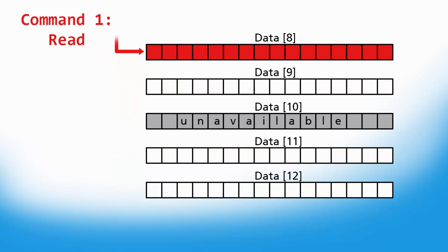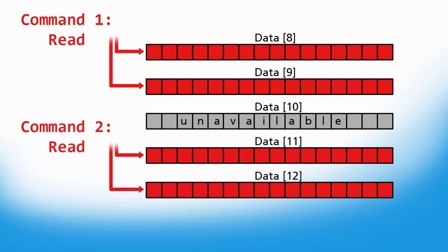You can test for this by changing the register count to 1 to see if the error clears. If so, then the solution would be to adjust your register count to ensure that you're only reading and writing to those addresses that are available. This may mean creating 2 or more commands to read and write registers up to the gap where registers are not available, and then pick up reading the registers after the gap.